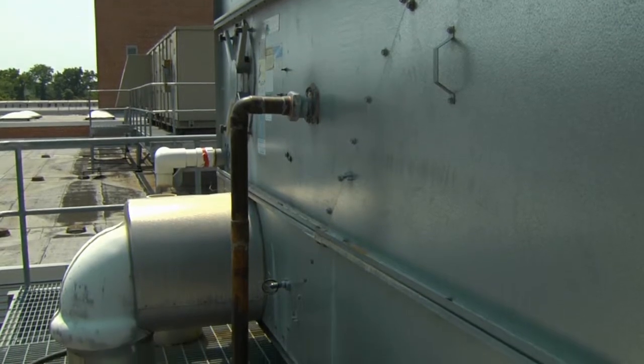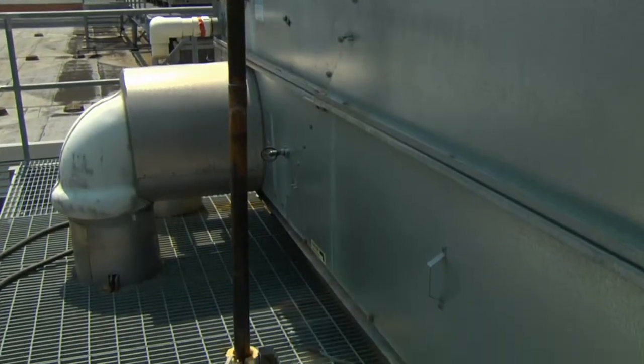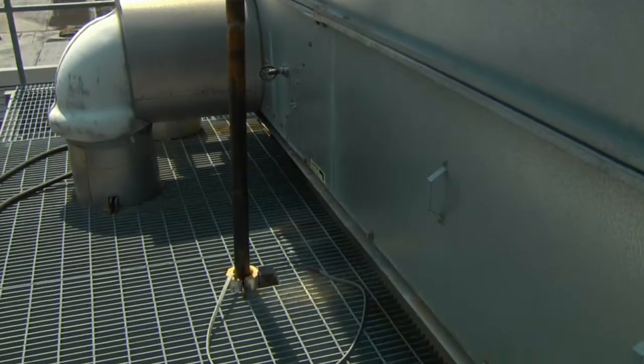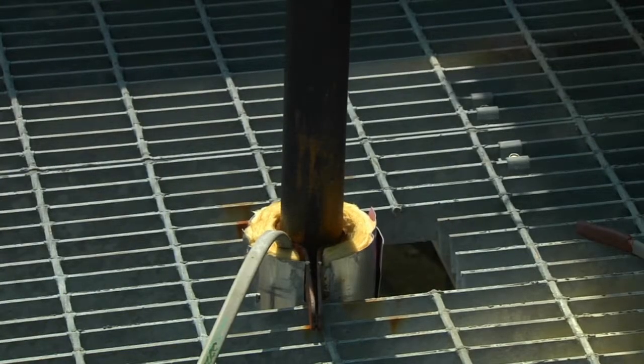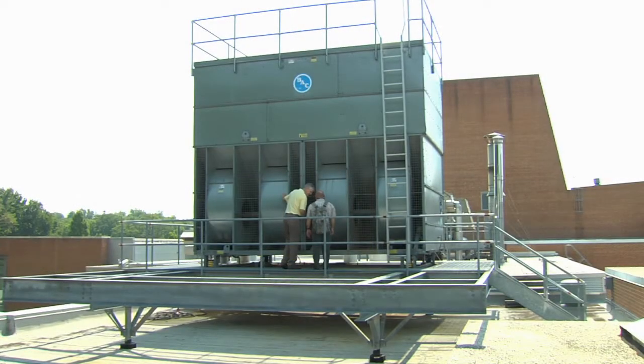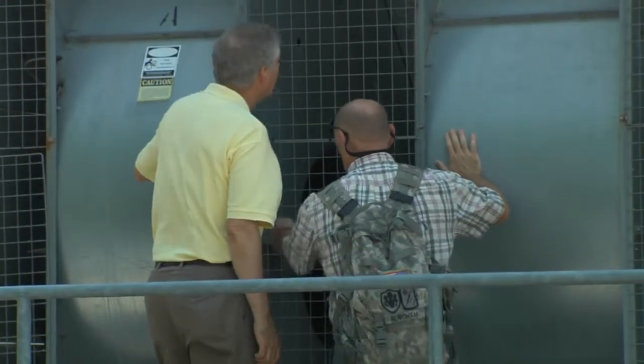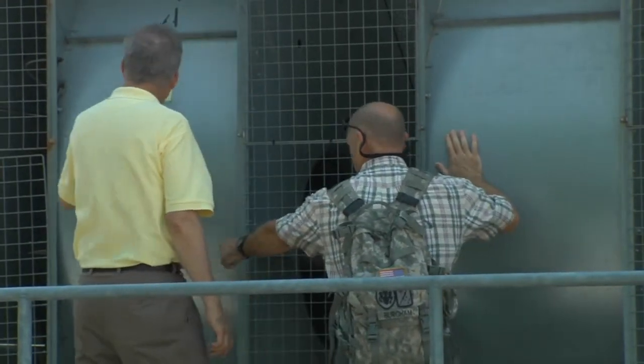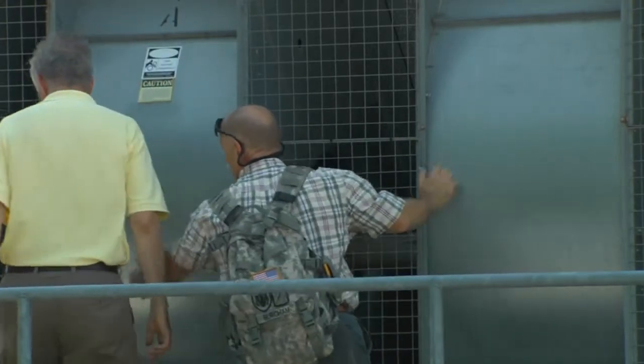The makeup water lines to the cooling towers were both frozen this winter, and the heat tape was exposed and the insulation was not replaced as it should have been. Steps are being taken to replace the insulation. At one of the towers, a fan shaft bearing was making a lot of noise, indicating a possible failure. Possible control improvement would be a condenser water temperature set point reset based upon outdoor wet bulb temperatures and the cooling tower's design approach.